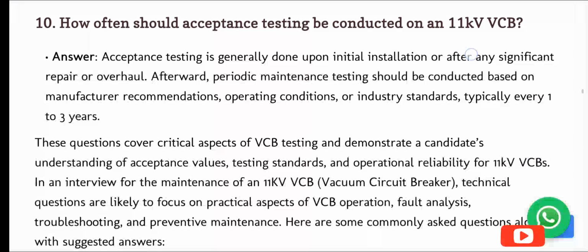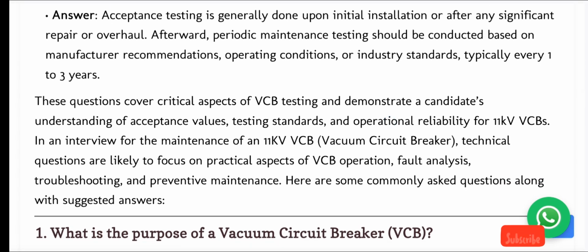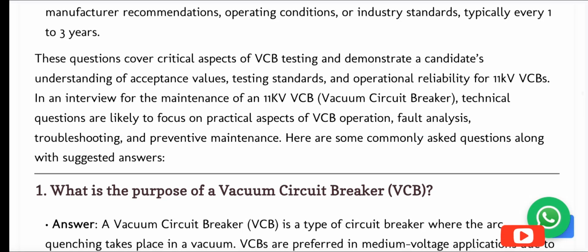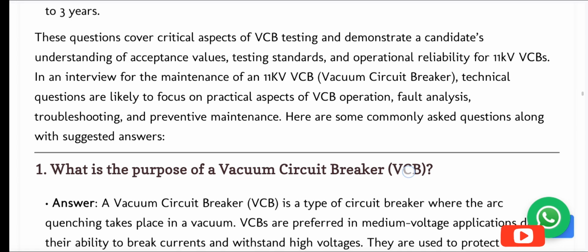10. How often should acceptance testing be conducted on an 11 kV VCB? Answer. Acceptance testing is generally done upon initial installation or after any significant repair or overhaul. Afterward, periodic maintenance testing should be conducted based on manufacturer recommendations, operating conditions, or industry standards, typically every 1 to 3 years. These questions cover critical aspects of VCB testing and demonstrate a candidate's understanding of acceptance values, testing standards, and operational reliability for 11 kV VCBs.